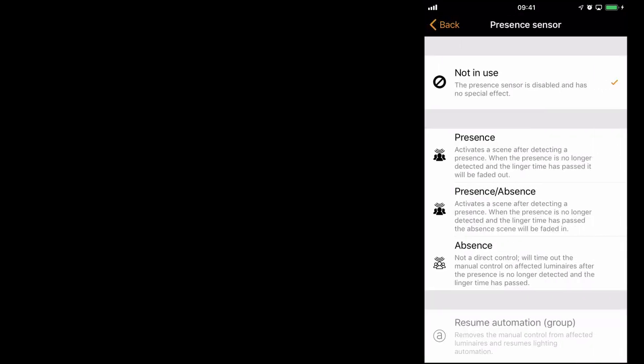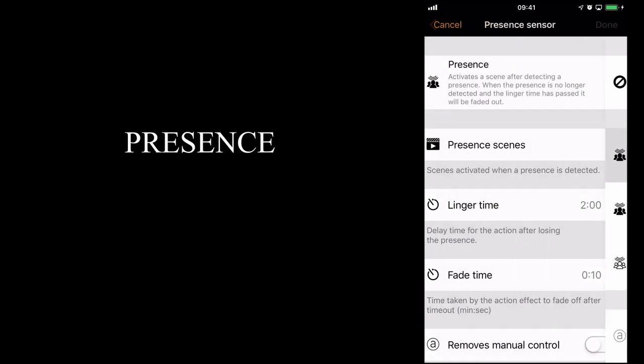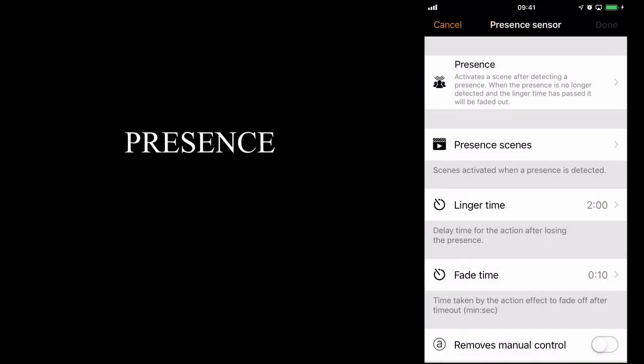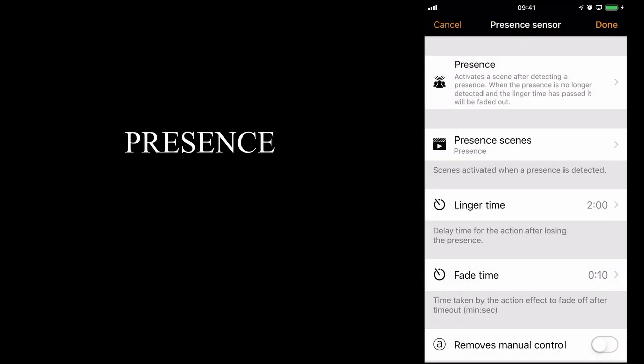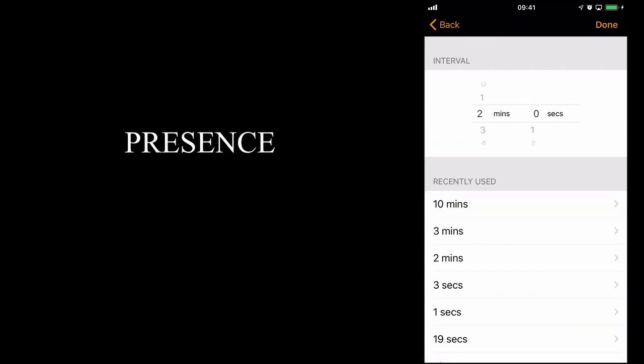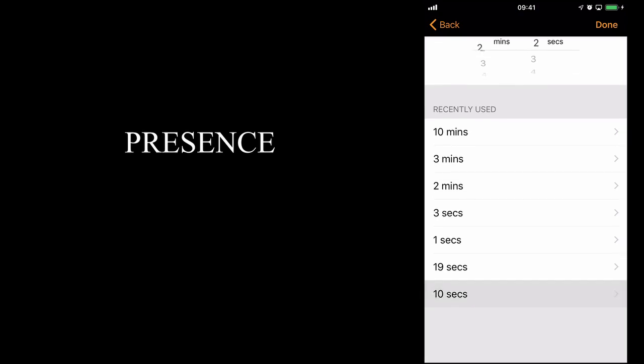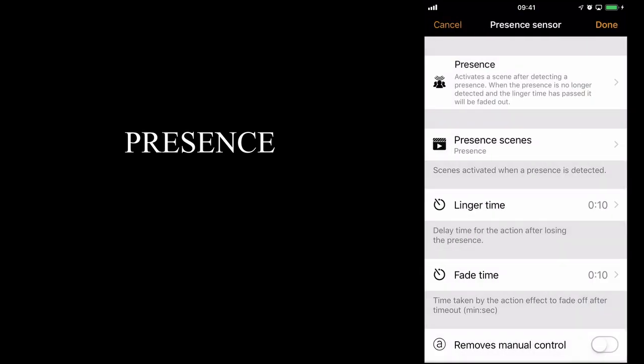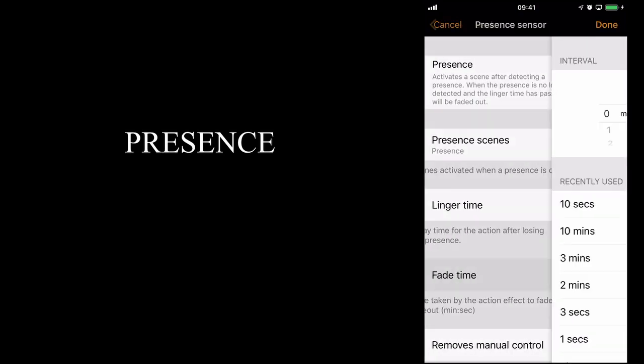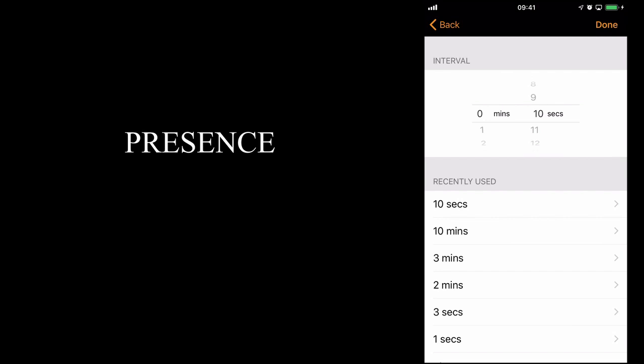We're going to take the first option, which is simply a presence sensor. We'll choose my presence scene, which will set the lights on to 100% dimming level. For the purpose of this demo, I'm going to change the linger time to 10 seconds and fade time to 1 second.